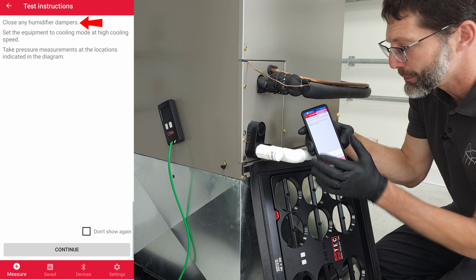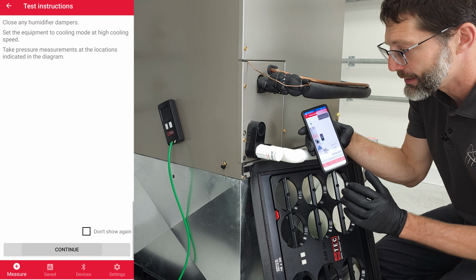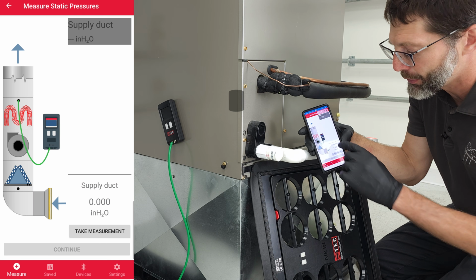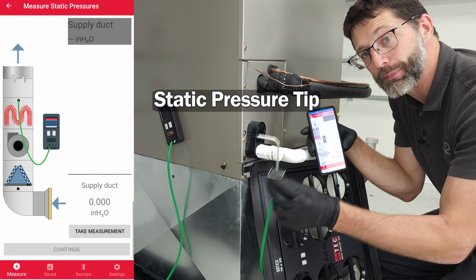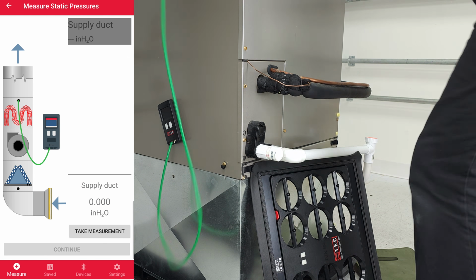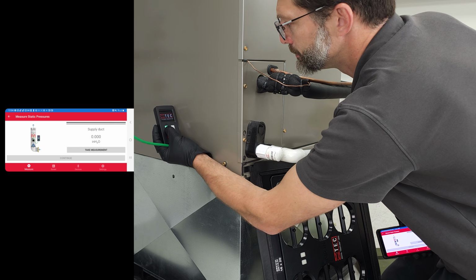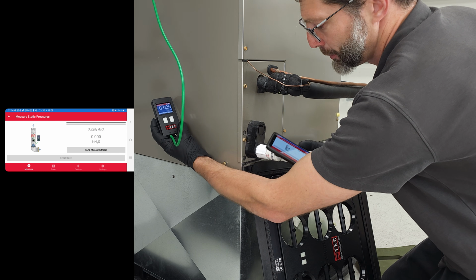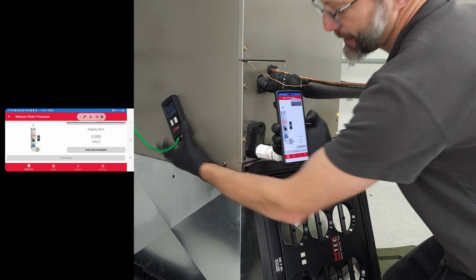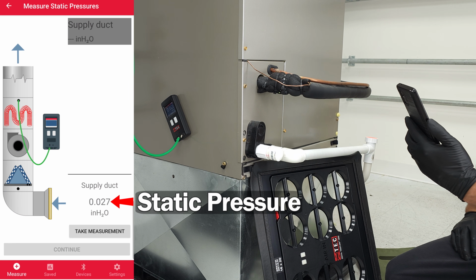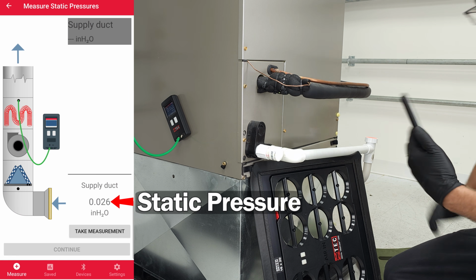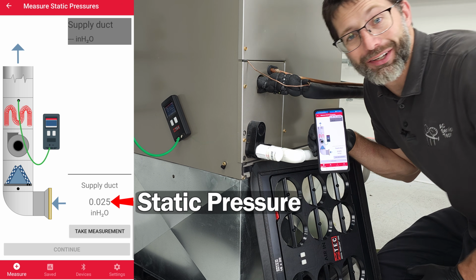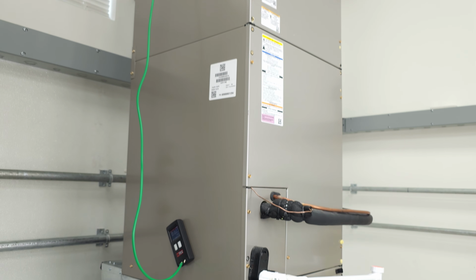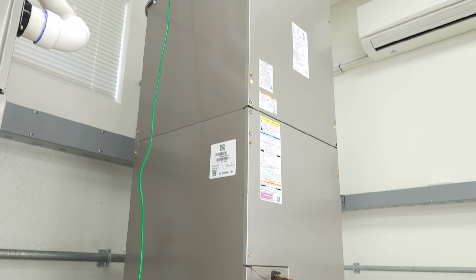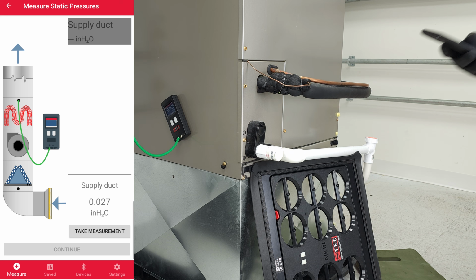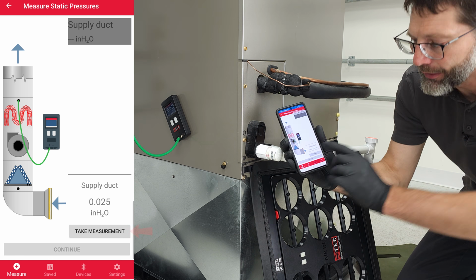It says close any humidifier dampers. We're going to go ahead and take our measurements. So we're going to put this static pressure tip in the supply duct. So we have a very low static pressure right now. Our static pressure is about 0.027. And the reason for that is there's no obstruction in the supply duct itself. This is just our little test air handler unit in our shop. We're going to go ahead and take our measurement right here.